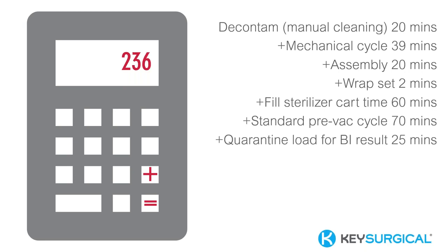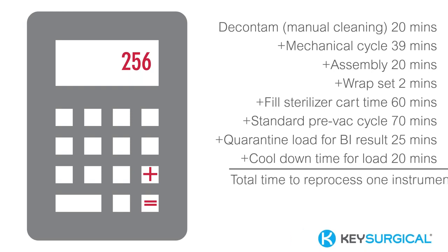Next up we have quarantine load for BI results. That can take around 20 minutes, depending on the BI you have at your facility and what the manufacturer declares as the proper readout time for the biological indicator. On top of BI results, there's a lot of metal and a lot of instrument sets that can be on one sterilizer rack at once. So it may take time after the BI results are read before they can cool down and be handled appropriately.